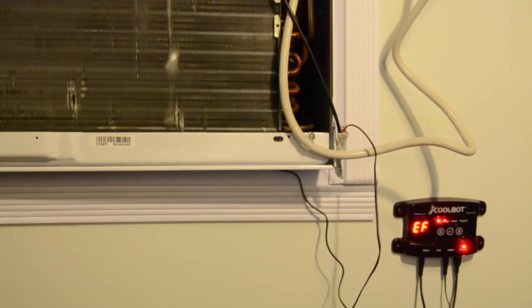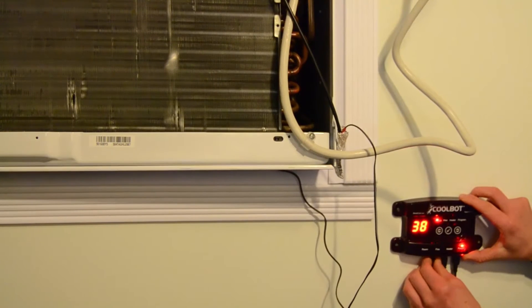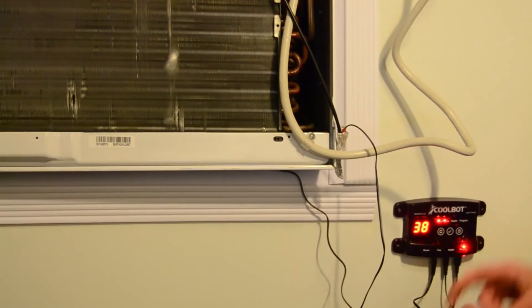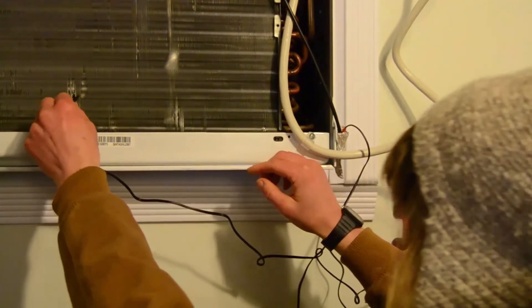We then want to use the room wire as our temporary fin sensor. Plug the room wire into the fin sensor's port and take the tip of the wire and put it into the fins of the AC. You can use the hole that is already there. Be sure to be careful so you don't damage or nick the coating.